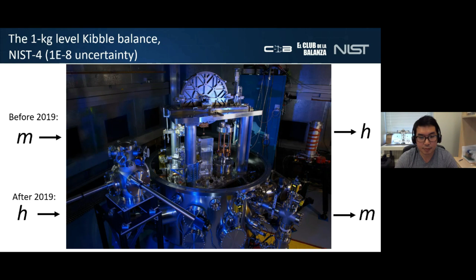And just by looking at this photo, you can tell it's really complicated because to get to 8 decimal places, you need everything that Richard was talking about earlier. You need the high vacuum environment, local gravity measurements, a robotic mass transfer system, a rack full of electronics, at least for us, that is as tall as the balance itself, and is tied to two quantum electrical standards, the PJVS and the QHR, the voltage and the quantum resistance. And these two devices, as we heard earlier, are where the Planck constant is buried in.